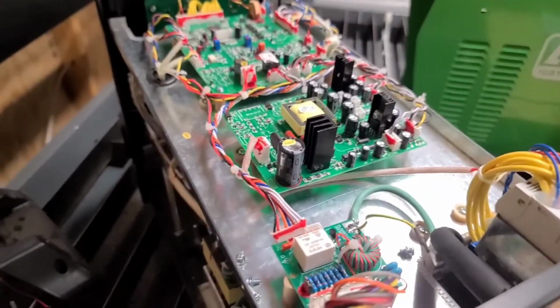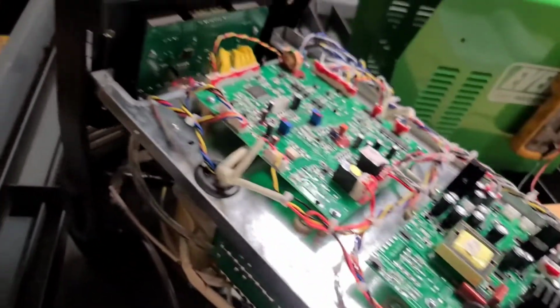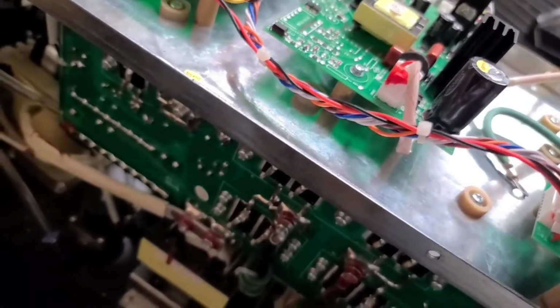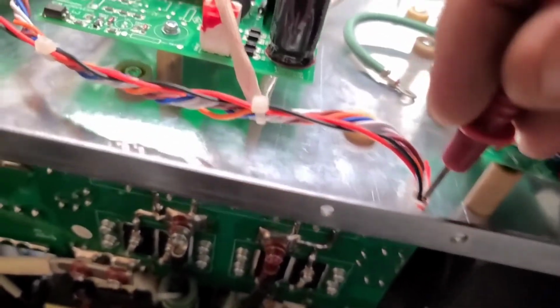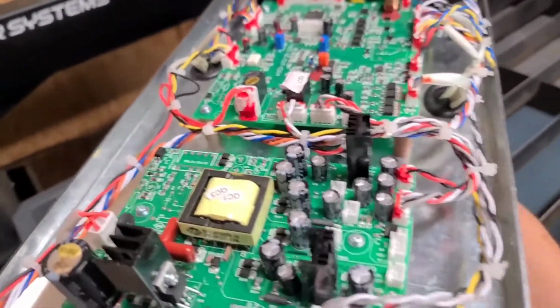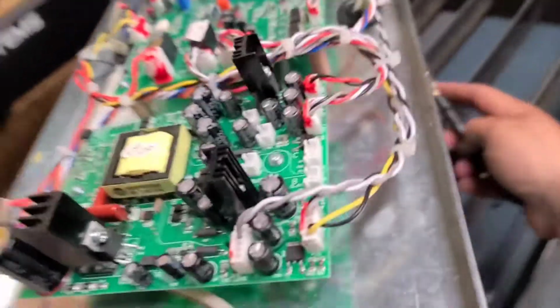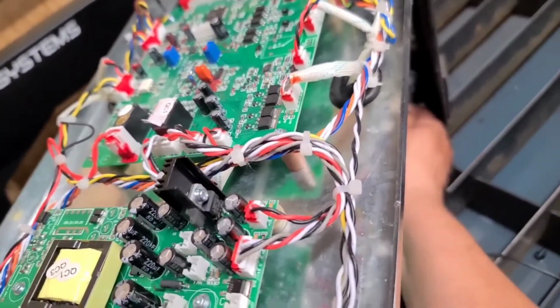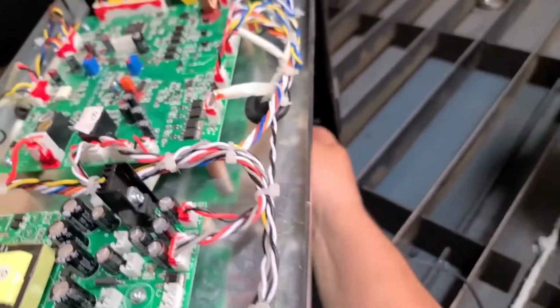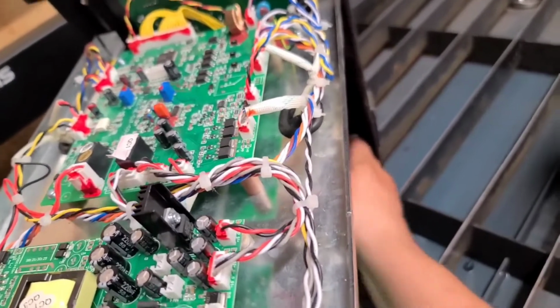So let's go ahead and check continuity. We have it hooked up on the torch head right now, and we'll just touch the back of this plug. It'd be easier if I got it off of there. Continuity. Now I'm going to move this lead onto the work clamp and show you what I was talking about.